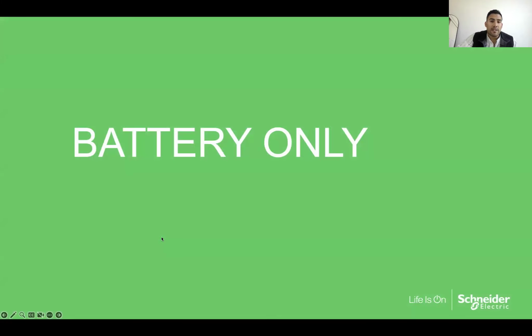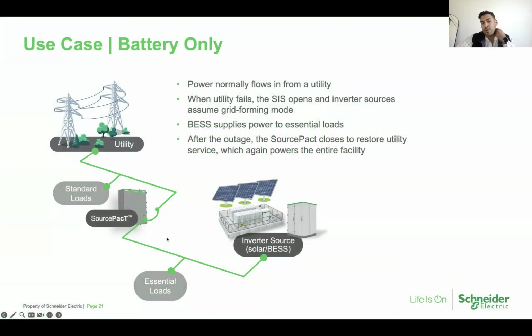So we're going to go through the battery only scenario. As I went through the operation briefly, SourcePaCT is designed to be downstream of the service disconnect, or downstream of your main switchboard, where you can isolate those essential loads to your battery energy storage system. Again, the battery energy storage system can act as a load during grid-tied operation, but it can also act as a power source. And the clever way that SourcePaCT does it, as an automatic interconnection switch, is that it automatically isolates from the primary service and allows those inverter-based resources to provide power solely to those essential loads, not throughout your entire facility. Otherwise we can deplete that reserve a lot faster.